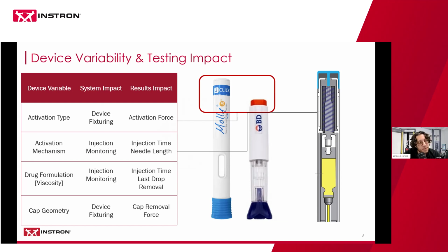And because of that, companies are investigating new technologies for activation that apply a much smoother force profile over the full travel of the stopper. So things like compressed air or electromechanical systems are starting to be used that will change that force profile to impart less force on the prefilled syringe inside the device. And this can have a major impact on the injection time, on the length of the needle, and how it pushes the syringe out of the device. All of that will impact how we develop the injection monitoring system.